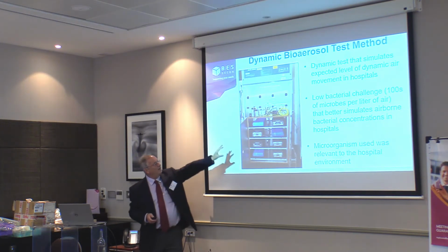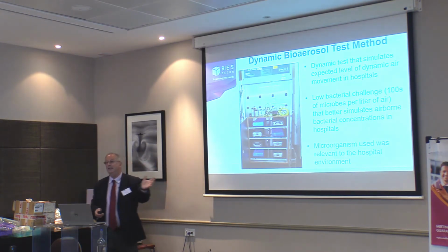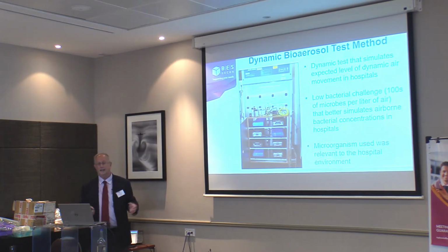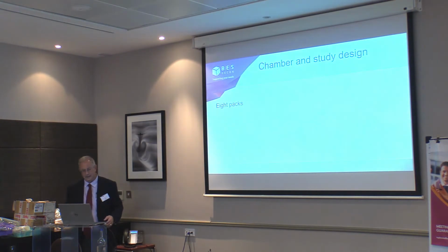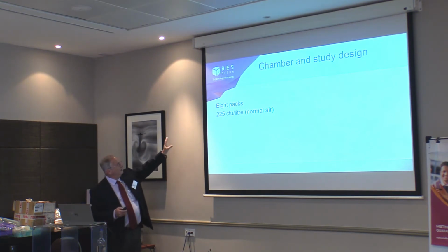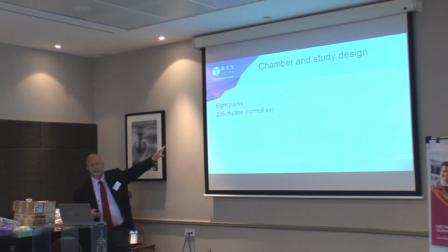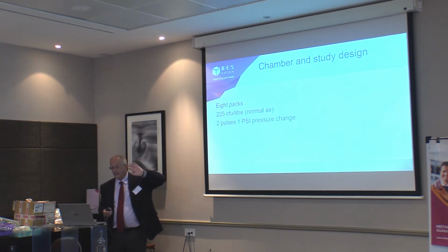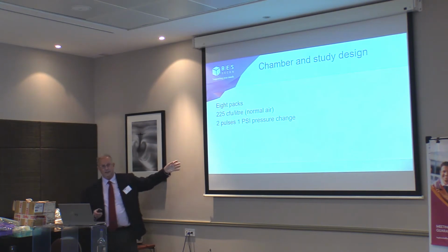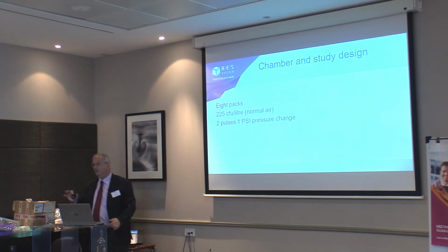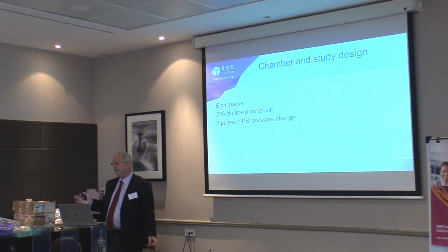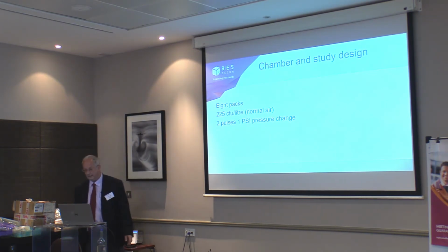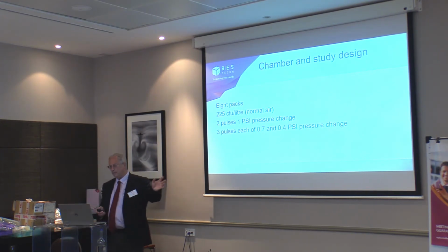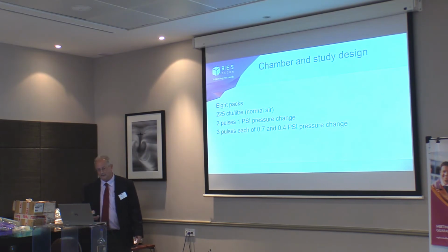He puts a bacterial challenge in there and then puts it through a simulated cycle of life for a couple of days to see what happened inside. So the pressure was changed. A bit more detail in a second. So they're designed to carry 8 packs at a time. They're putting in bacteria at 225 CFU per litre, which is about what you find normally in air. And then he had 2 pulses of 1 psi pressure change, but normally the study has shown that you probably in normal use get up to 2 psi, so this is not the full stresses normally seen. There's 3 pulses each of 0.7 and 0.4 psi pressure change, so there's a total of 8 pulses.